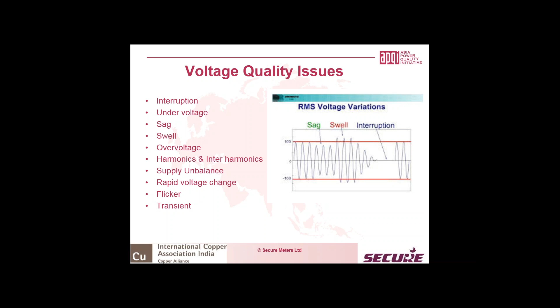Similarly, swell is a temporary increase. The duration may again be from half a cycle to a few seconds, whereas a transient is a high amplitude, short duration millisecond spike which gets superimposed on the normal voltage or current. It's also usually referred to as a spike. And flicker is a visible change in brightness of a lamp or a computer screen due to rapid fluctuations in the voltage of the power supply, and this can also have a huge impact on the productivity of the industry. So all these are the basic voltage quality issues which an industry or a commercial establishment can experience.